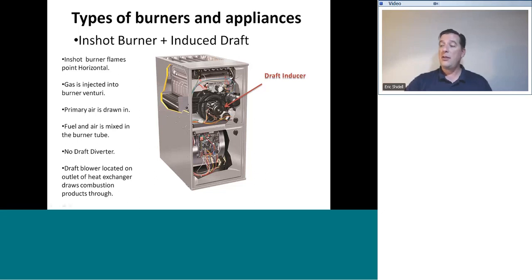As a result, now the inducer is often on the bottom of the furnace and the burners are on the top. You can see the serpentine arrangement of the heat exchanger, how that passageway goes back and forth and then up and down, back and forth, and then back and forth through the secondary heat exchanger. All the while, the draft inducer is pulling those combustion products through that convoluted pathway. These are built this way to give the heat exchanger more surface area, so that it is better able to reject all of that heat of combustion to the airstream that's passing across the outside of that heat exchanger.